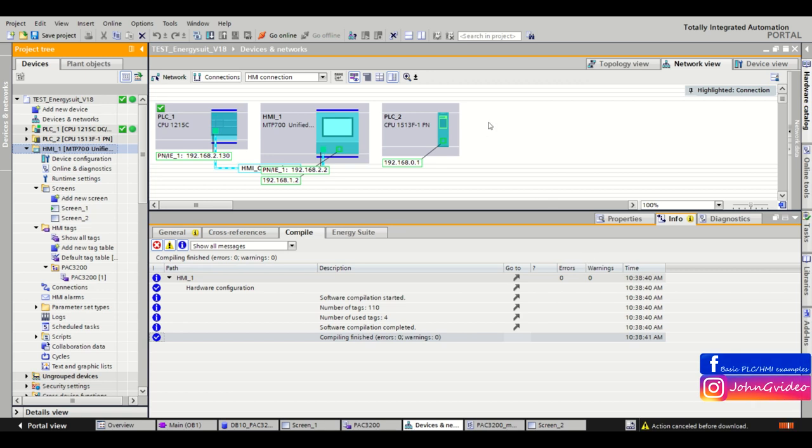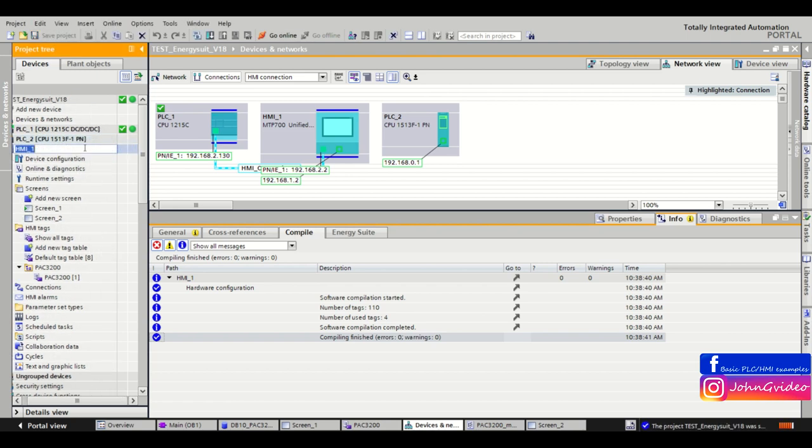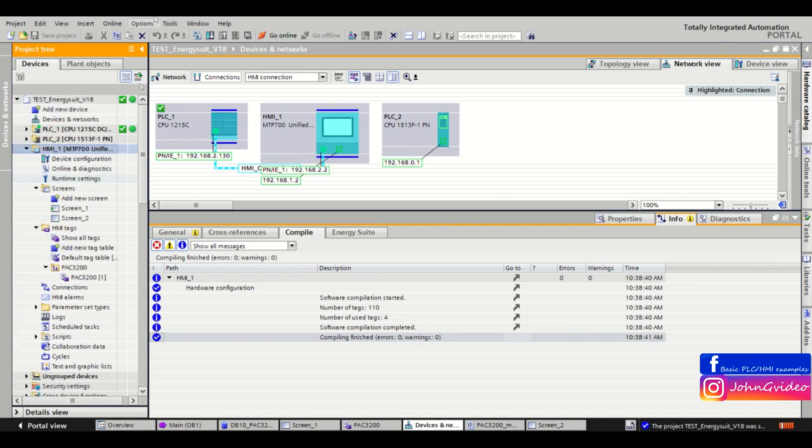Upcoming video where I show you how to solve a problem about downloading your HMI application to your unified panel. This error is incompatible firmware image. So we have a project with a unified panel.